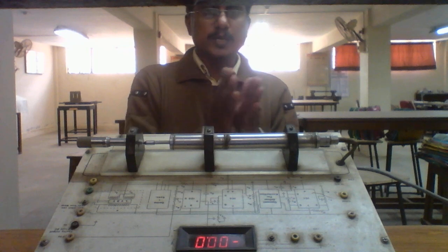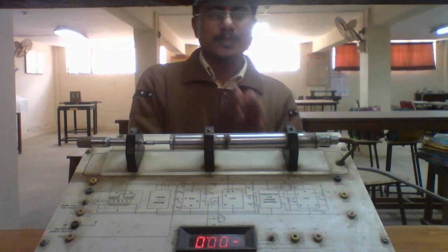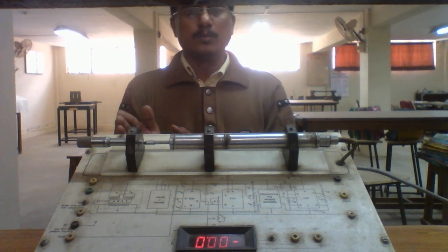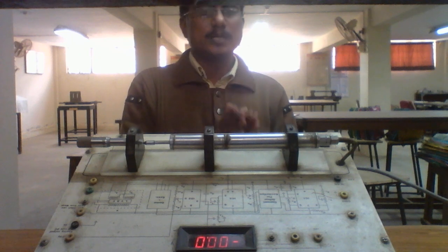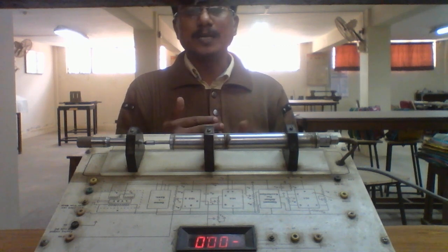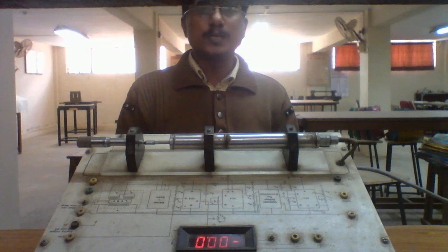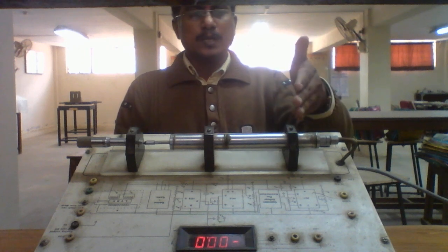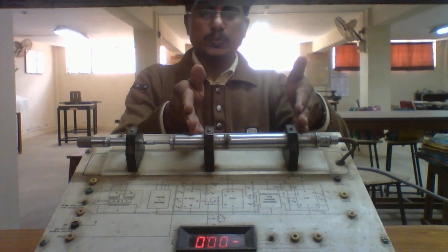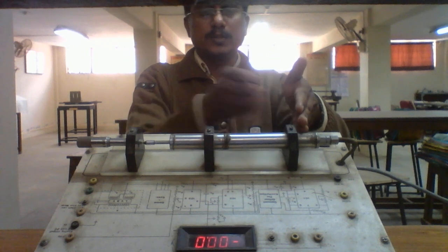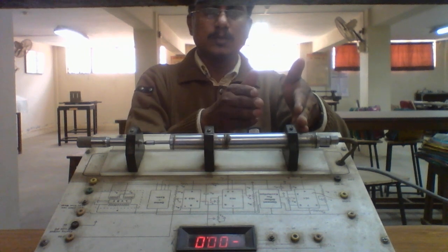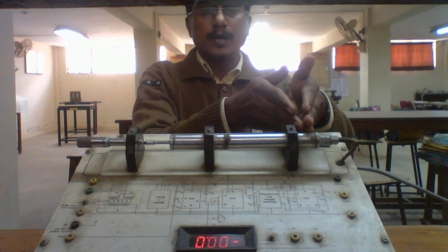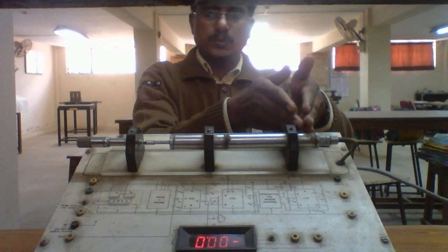It has two modes of operation: null displacement and displacement. The displacement is of two modes: left hand displacement and right hand displacement. Here we are observing the linearity and hysteresis in the instrument readings. Now we will give the forward displacement, where this is S1 and this is S2. S1 will be more active than S2, so the output will be given by the instrument based on the excitation of S1.